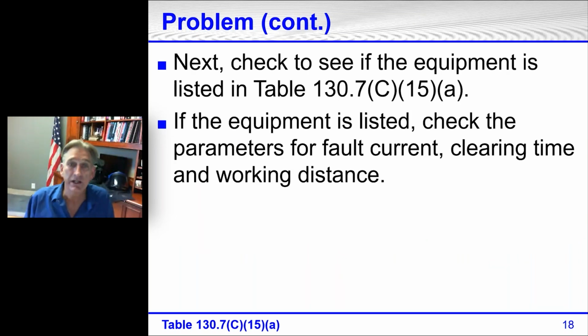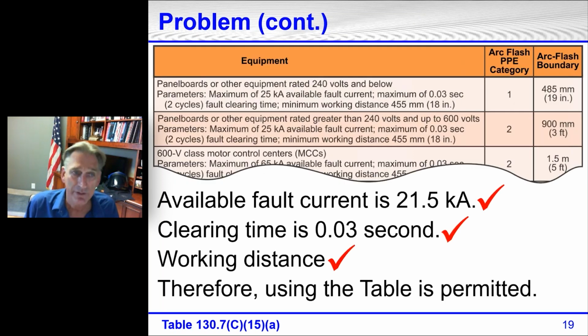Next, check to see if the equipment is listed in table 130.7C15A. If the equipment is listed, we have to check the parameters. All right, so the panel board, the second row, panel board or other equipment rated greater than 240, because our panel board is 480, up to 600. All right, I gave you the available fault current at 21.5 kA. The maximum is 25. Check, we're good there. The clearing time is 0.03 second. Check, that's exactly our maximum. And then the working distance I gave you is 18 inches. Therefore, yes, we can use this table.